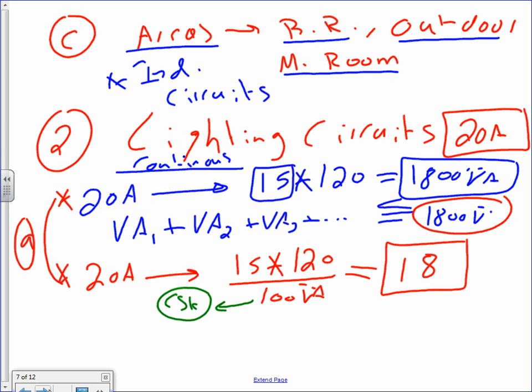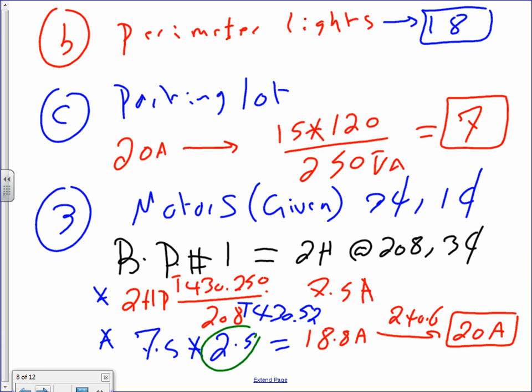Yes, no? Okay, all right, so let's go to lighting, 18 on the 20 amp circuit. Perimeter lights. The perimeter lights, guys, are the security lights around the building. Typically the same thing, 100 volt amp. So I threw in another 18. If you have 18 of them around the building, put them on a branch circuit and feed them up to 18.